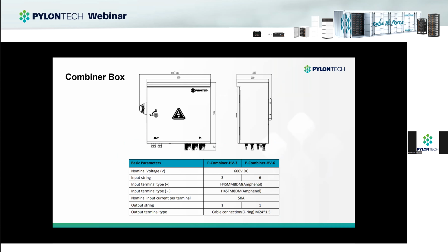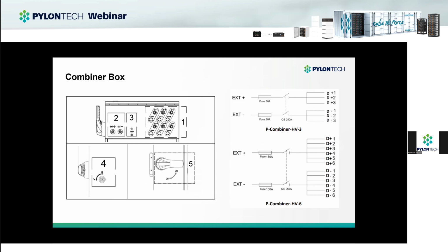We can also provide this combiner box in two models. HV-3 means it can support three strings, and HV-6 means it can support maximum six strings for the batteries. You can see they have a fuse on each circuit, and for the whole combiner box, it has a big DC breaker, so that means you can have a stable breaker connection and disconnect connection between the batteries and the inverter.